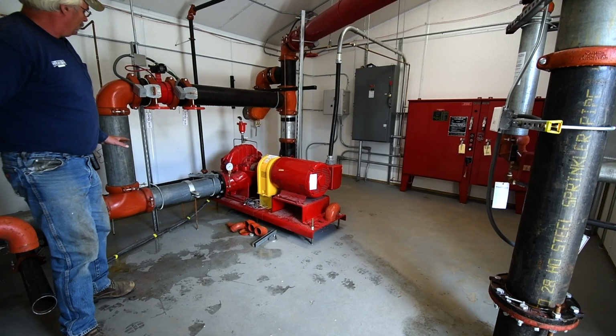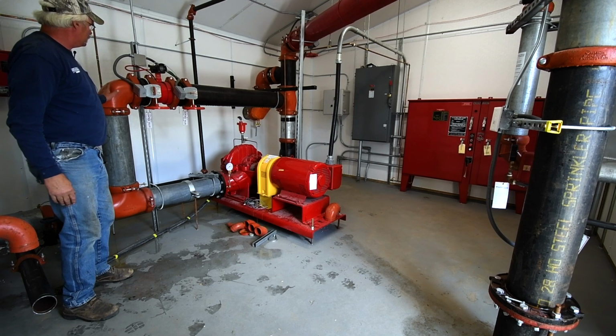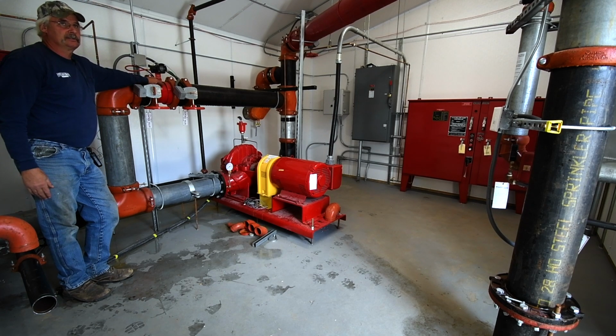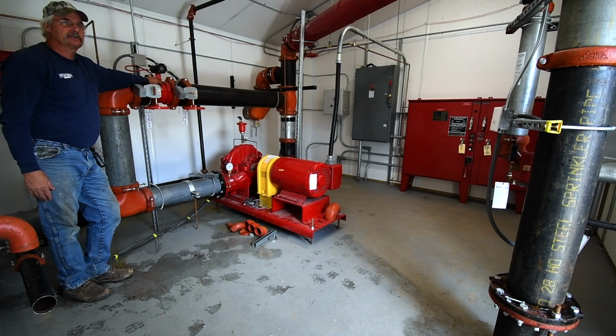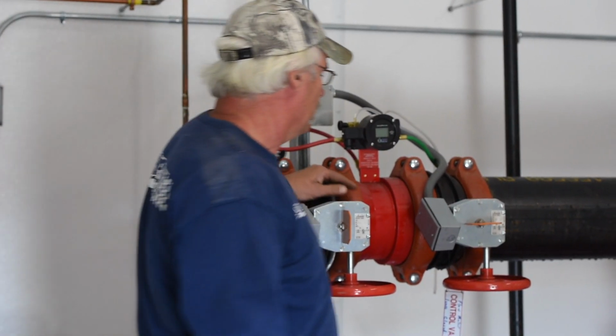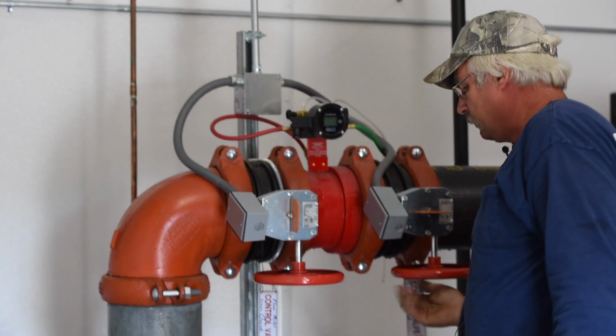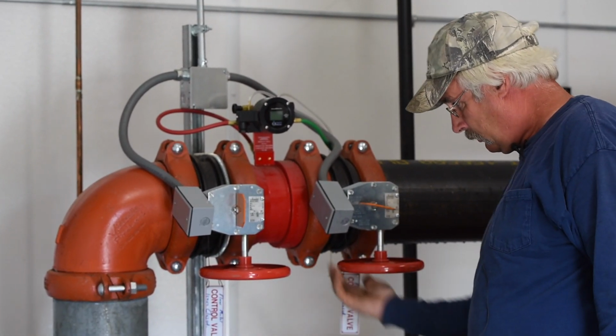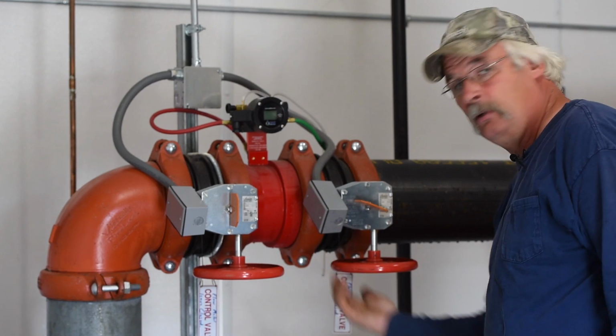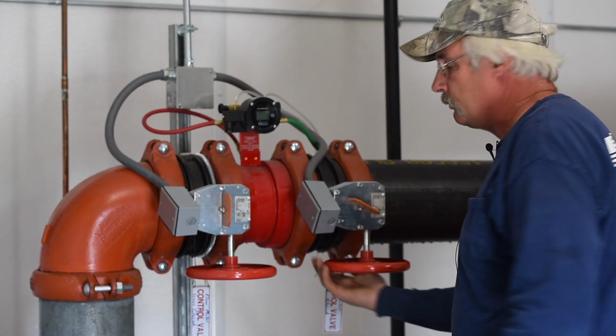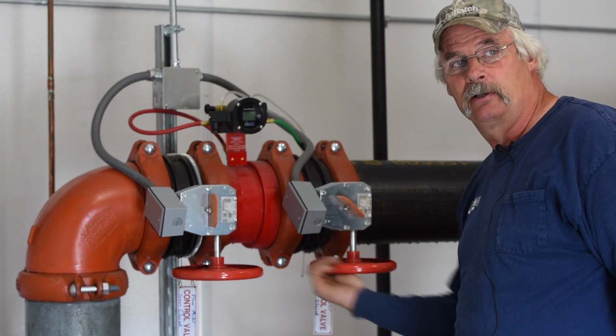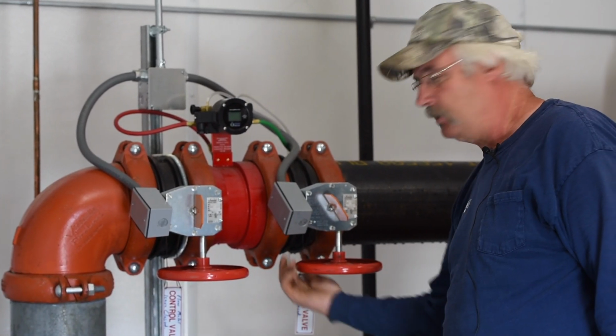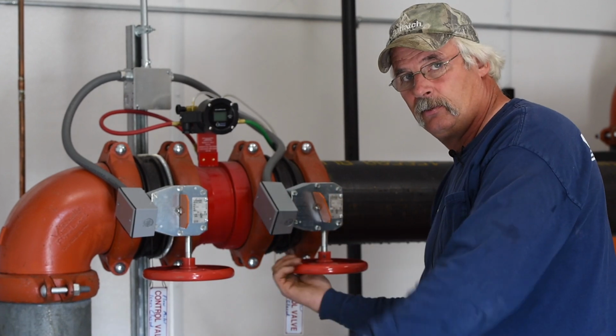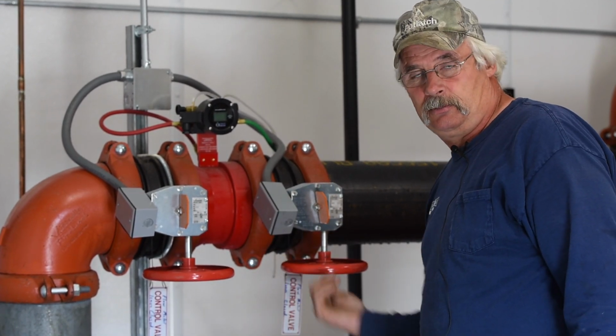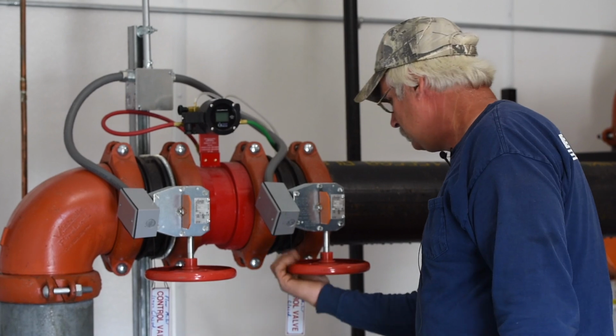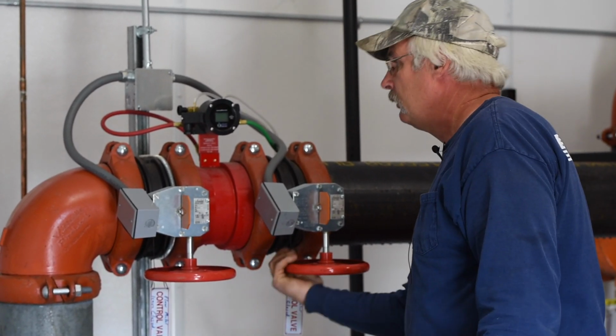A little bit more on the fire pump here. This is actually a flow meter. This is during an annual test, so this will be serviced. These 2 control valves here will be normally closed. It says right on here, normally closed. What these 2 are for is just to bypass over the fire pump and running water. Instead of pushing it out through a test header, we can actually churn the same water out of the tank and roll it through the pump to complete our annual test for fire protection on the pump.